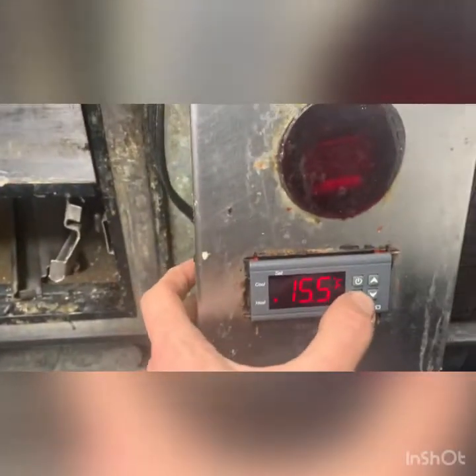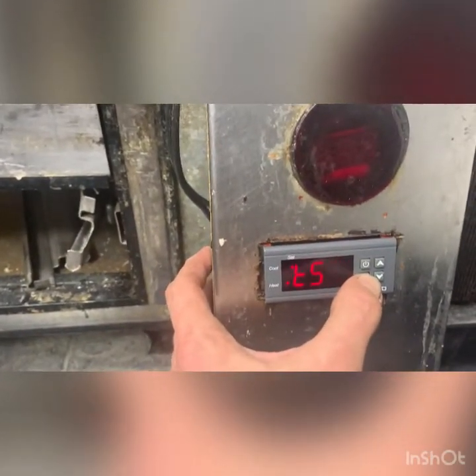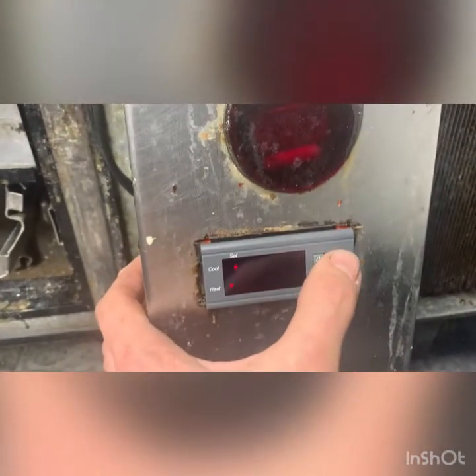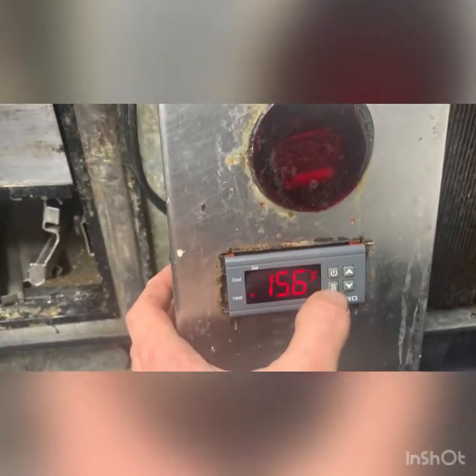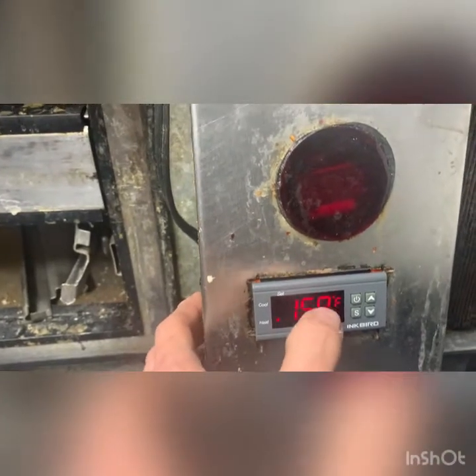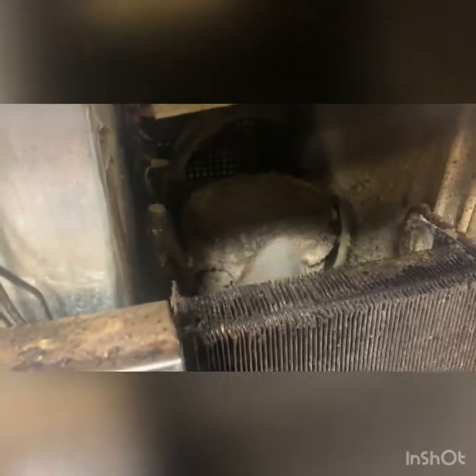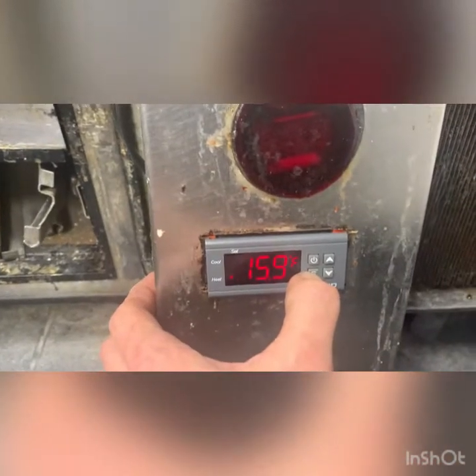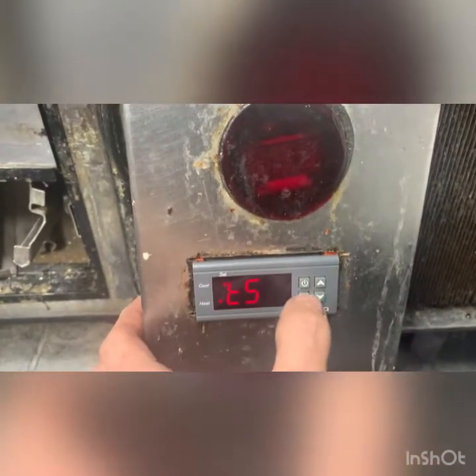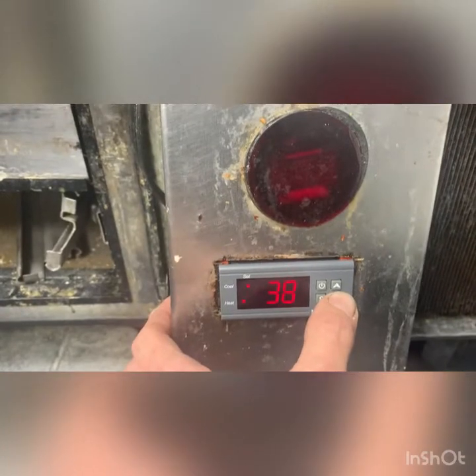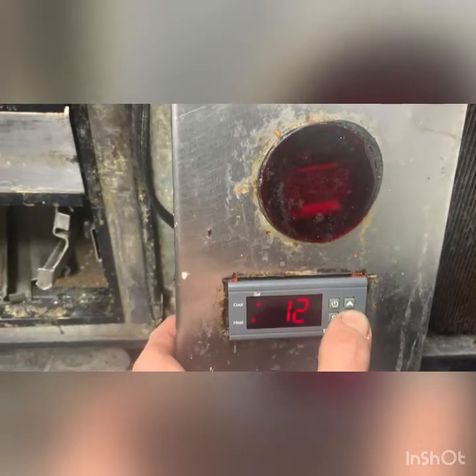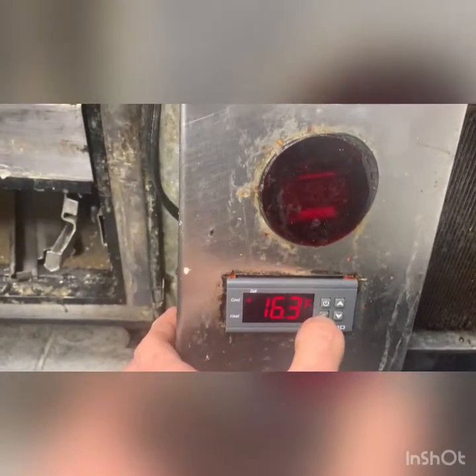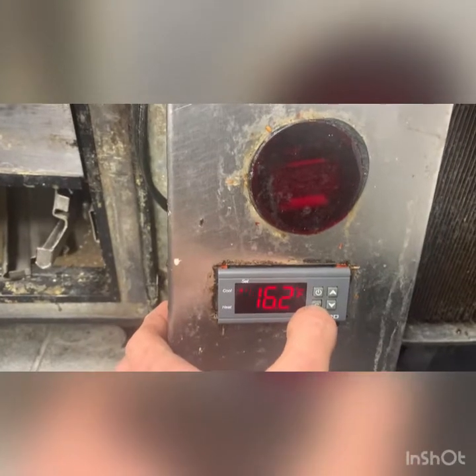I'm going to leave these doors off. That's the temperature setting, right? 50, beautiful. I'm going to leave it at 50. Until that's above 50, it's not going to cool. Remember, last time it said negative 16, but also this was running. So these are not running now. If we want to test that I've got it wired up properly, let's do that. Temperature setting, we were at 15, right? So if we shut this down to 8 and set it, green fires up. So I know the thermostat works properly.